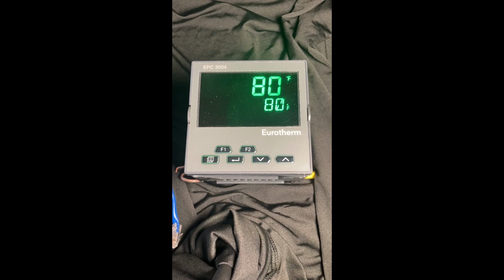I'm trying to control a process one day at, for example, maybe 300 degrees, and I'll set up the auto tuning and it works great. But then the next day, I'm trying to control this same oven at maybe 600 degrees, and now the PID settings don't work, so I have to re-auto tune. Is there a way that I can control different processes without having to re-auto tune? And the short answer is yes.